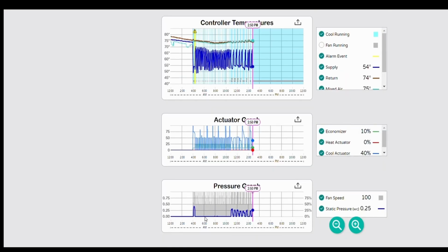It looks to me like this static pressure probe is probably in a bad spot. You can see if you zoom in how these are a little wider here. When you have a nice long call, this call is maybe half an hour or so. But these little short calls never build enough static pressure to register on the sensor. Even during these longer calls, it only builds to 0.25 or 0.3 inches of water column, which is nothing.